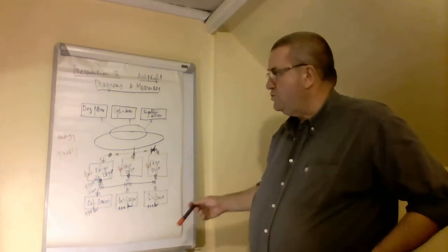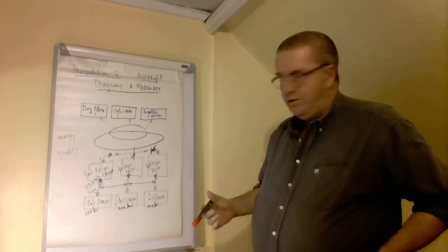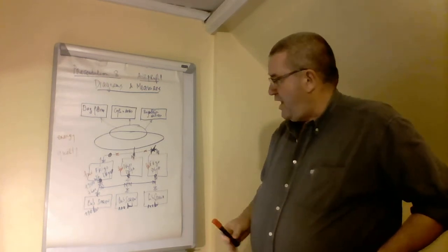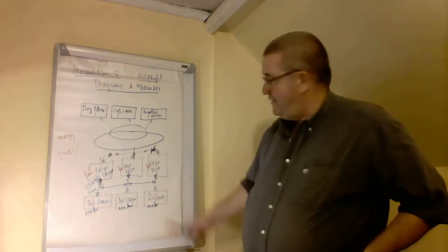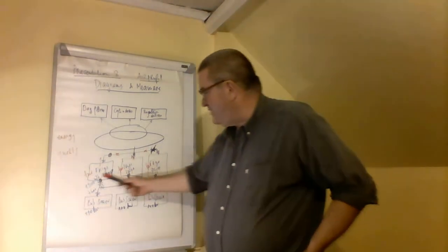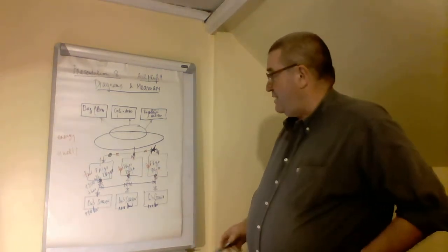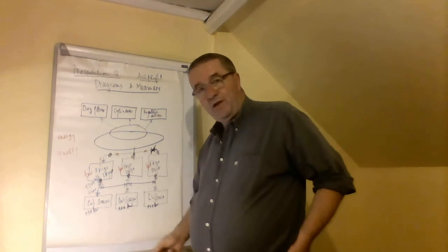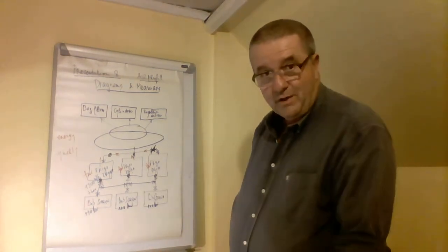This was something very usual in the past with what we called thermal mass frigorific dryers. They could have an electricity consumption which was proportional, and this diagram is not very favorable to energy efficiency, except if you put in very efficient dryers, for example variable speed dryers.